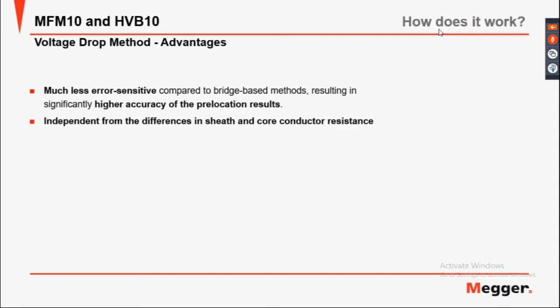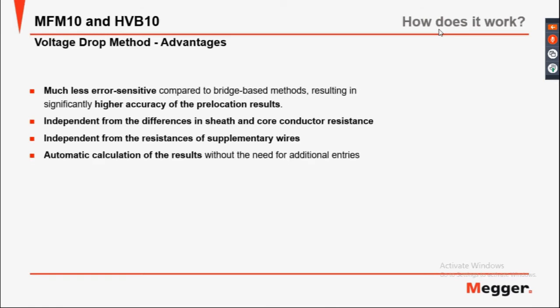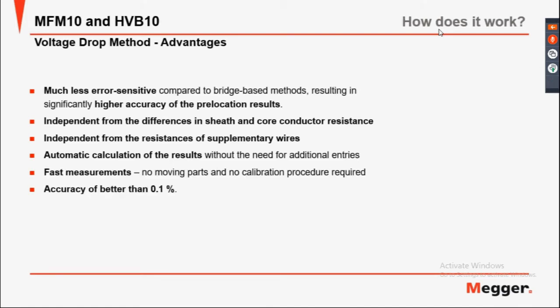The volt-volt method is independent from differences in the sheath and core conductor resistance, and independent from the resistance of the supplementary wires. It provides automatic calculation of results without the need for additional entries, fast measurements, no moving parts, no calibration procedure required, and accuracy of 0.1% or better.